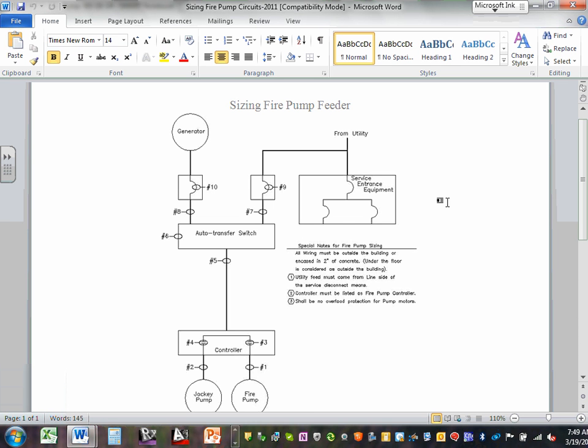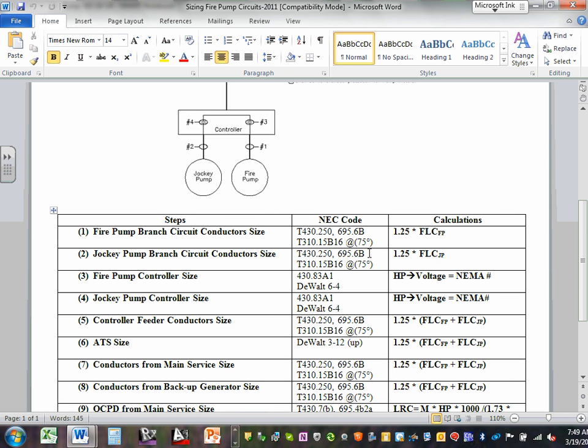All right. So like I said, this guy's sizing fire pumps. For fire pumps, when the mechanical engineers and the sprinkler guys decide that the water pressure in this building is not high enough to run your sprinkler system, what they do is they install a fire pump. So two things to know about the fire pump.